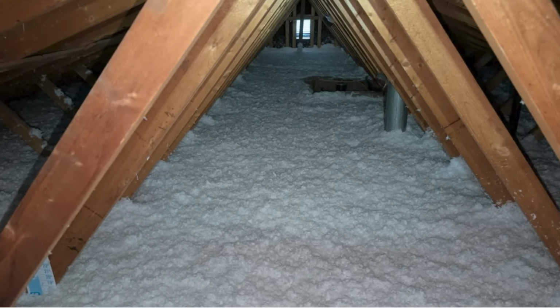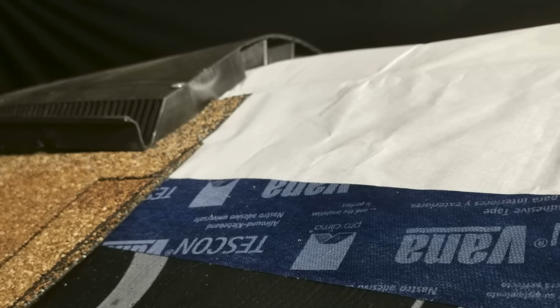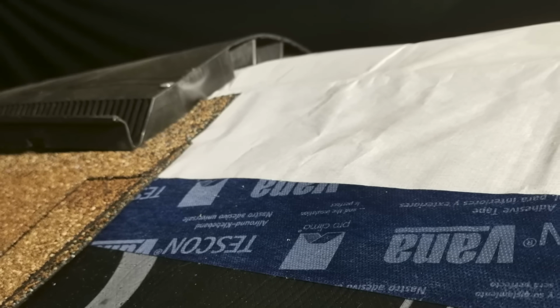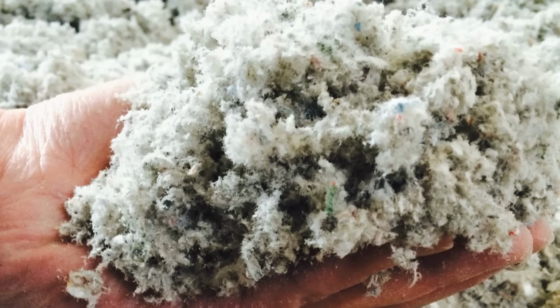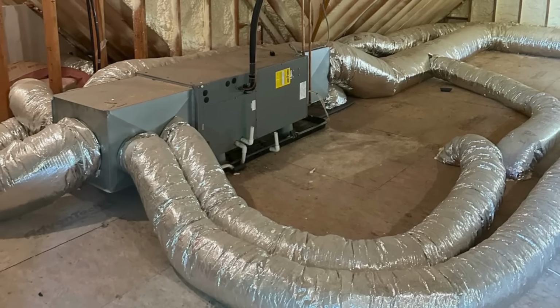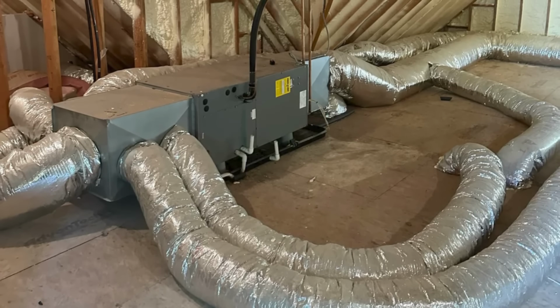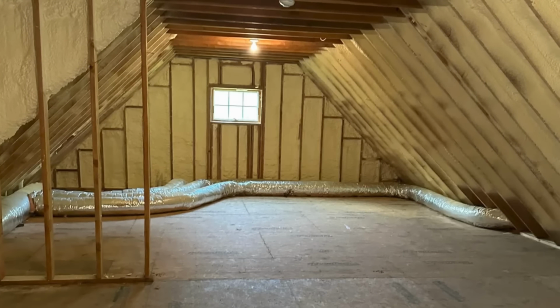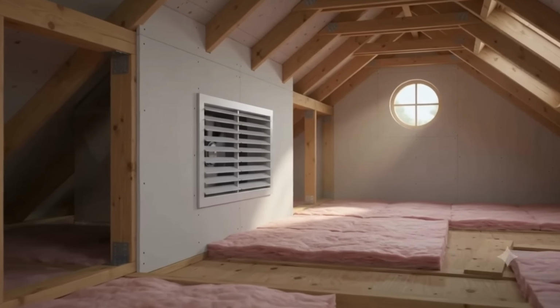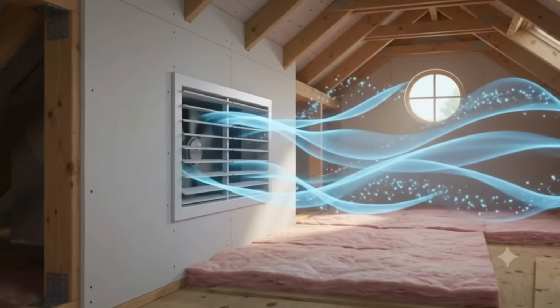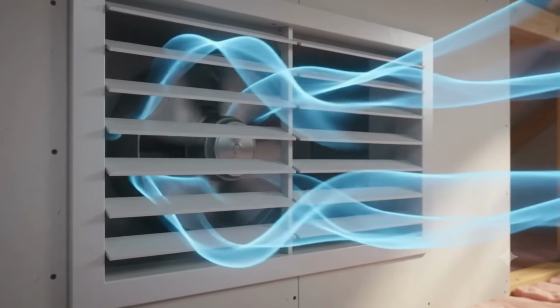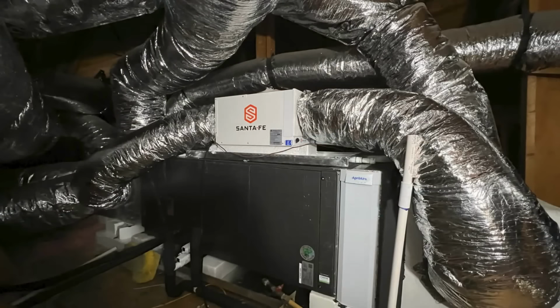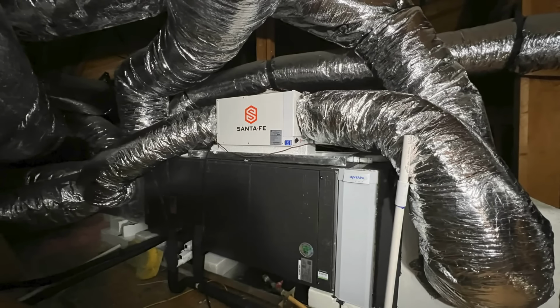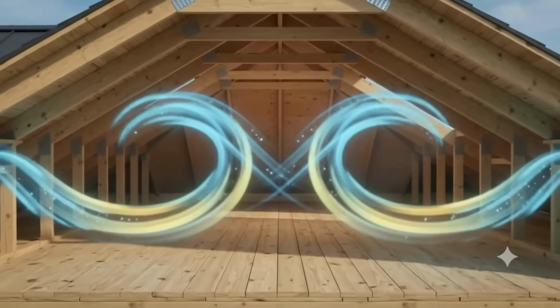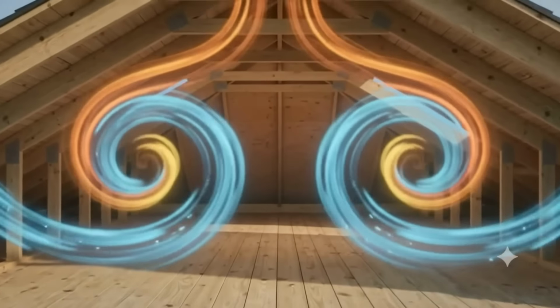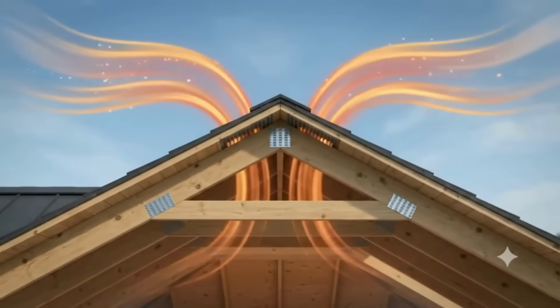This isn't the same as a vented attic or vented roof. This is just a mechanism we're using to remove the moisture that passes through the diffusion port. Now, because you're using air-permeable cavity insulation, you need to provide active conditioning to the attic space, and this is true of any conditioned attic, but it's especially important with this strategy and required by code. This is typically accomplished by delivering a small amount of supply air, at least 50 cubic feet per minute for every 1,000 square feet of ceiling area, or by installing a dedicated dehumidifier in the attic or both. Basically, we want to get dry air circulating in the attic space to address any moisture buildup so that our diffusion port isn't being completely inundated.